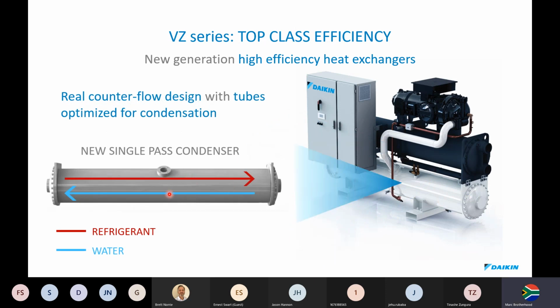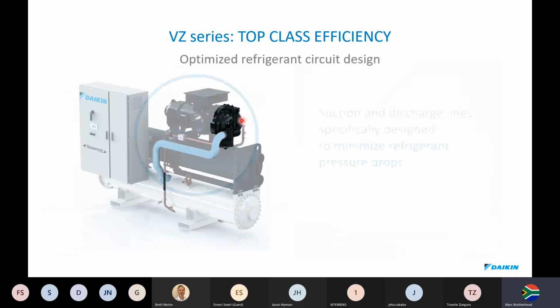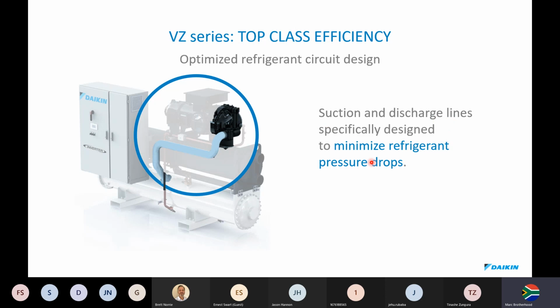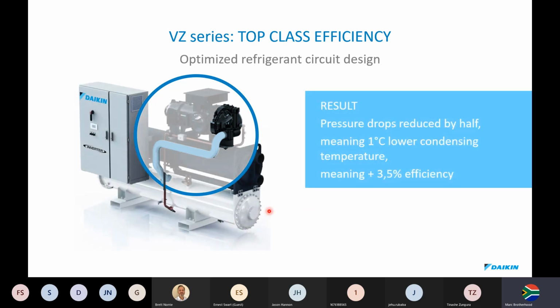An important feature in the condenser is a single pass, parallel single pass, which is a real counterflow design, and the tubes are obviously optimized for heat transfer and heat exchange. Our suction and discharge lines are specifically designed to minimize refrigerant pressure drops. So what does that mean? Even in the short bit of pipework, pressure drops are reduced by half, meaning that we have a 1 degree lower condensing temperature. By lowering the condensing temperature by 1 degree, we increase the efficiency by 3.5% just by tweaking that discharge pipe out of the condenser.